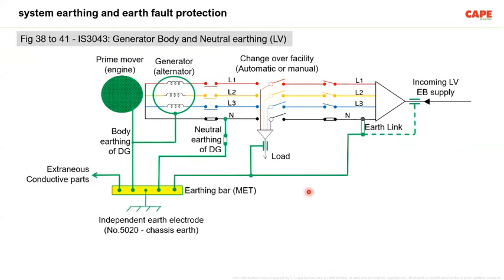What is the correct way of earthing of a generator? You can see here pictures 38 to 41 of IS 3043. The DG body and the alternator body are interconnected together to an earth electrode, sorry, to a bus bar, an earth bus bar. Neutral is also connected to a bus bar. The incoming EB supply earthing, TN-C-S, is also connected to the bus bar. The load side earthing is also connected to the earth bus bar.